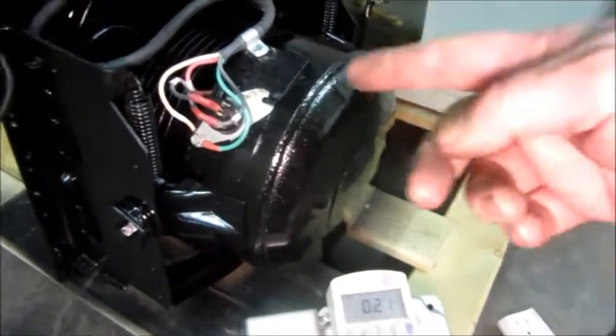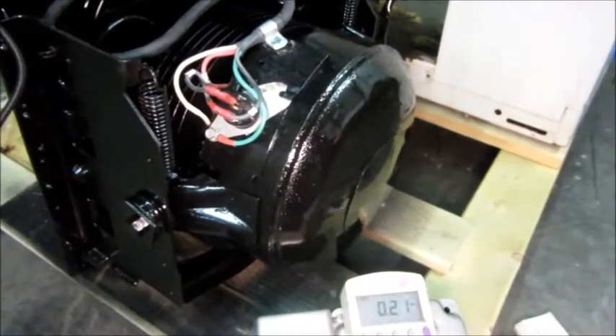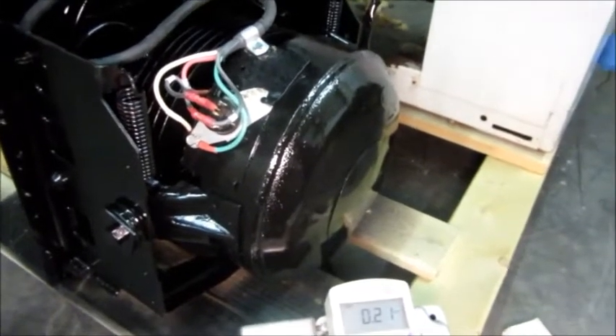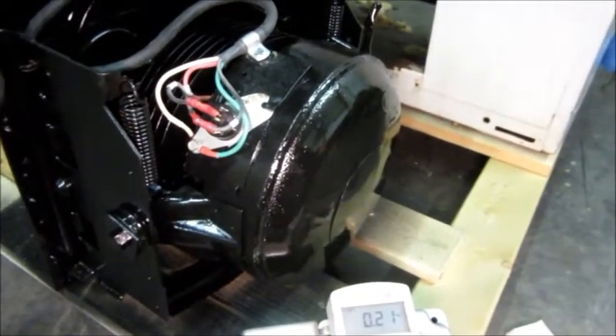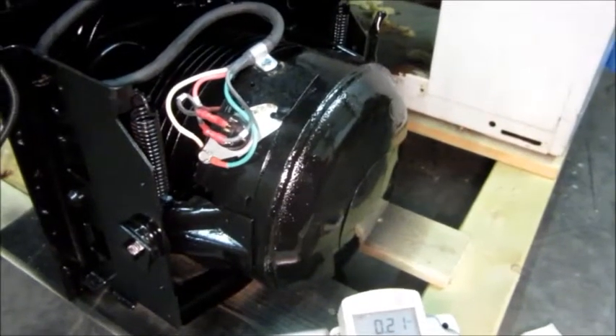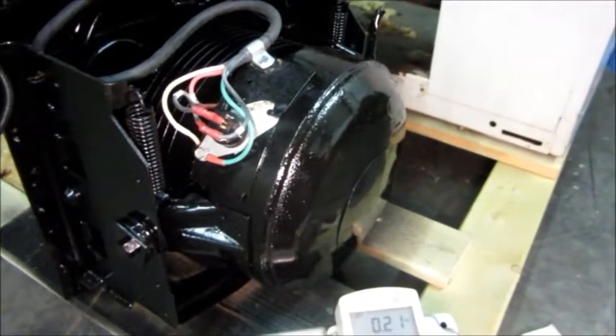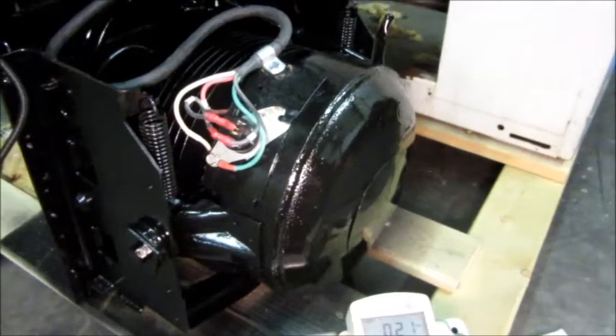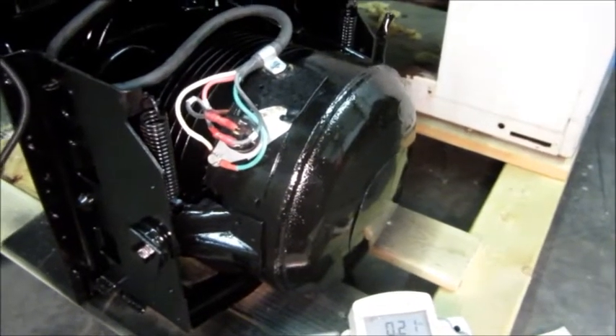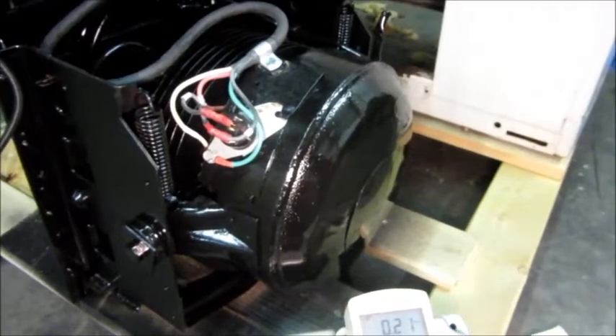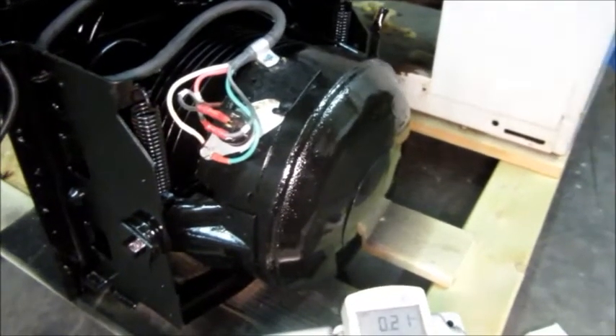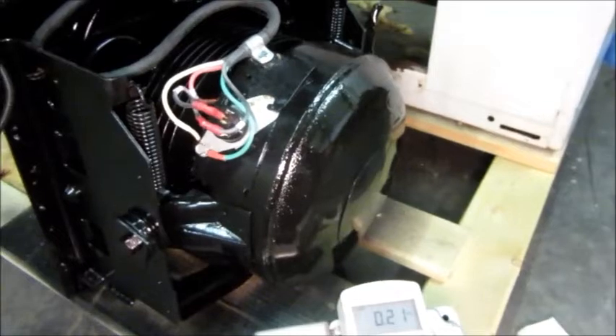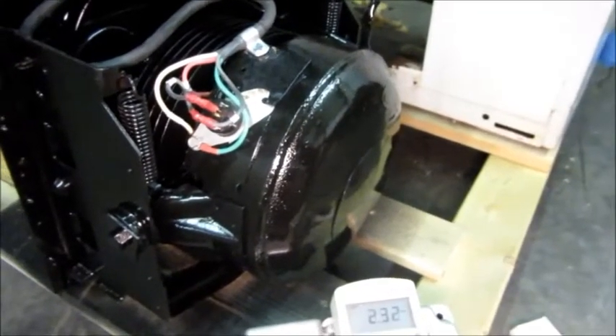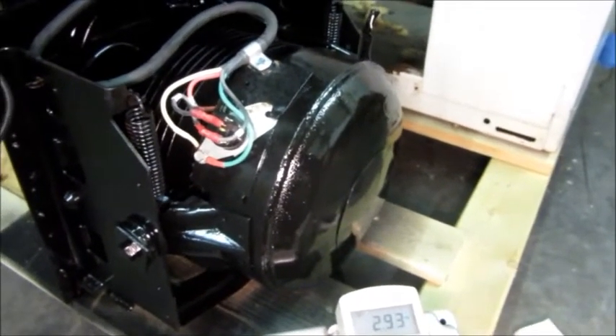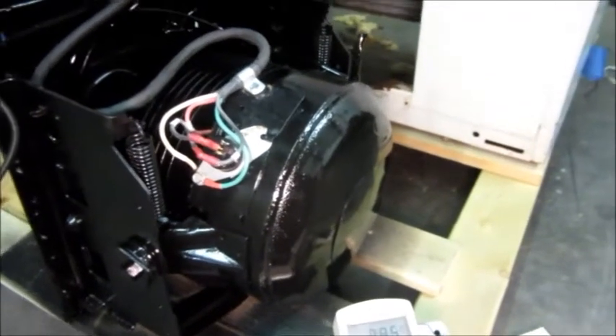So during this time, the overload breaker is cooling off and resetting, and the pressure is equalizing in the system. One thing I like about the Supco overloads, they have a long reset time. Gives the motor plenty of time to recover and cool off from that first failed start attempt. So, stall test is successful. That's one more check in the book, and go for a shutdown.